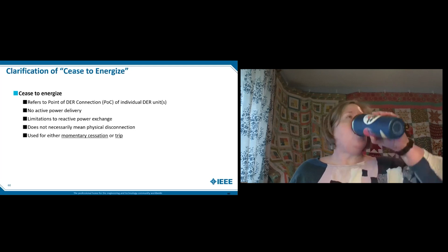Now, I worked for a utility where at solar noon on suburban feeders, where everyone's at work or gone and PV is at maximum output, we were getting voltage lift to the point that, yes, we had to stop adding PV. And we didn't use voltage regulators or load tap changers. But here's an interesting idea in Alaska. Solar noon could go for many, many hours during the summer. So I would imagine there could even be more drivers to make sure that they're leveraging, accessing, and using the voltage VAR controllability, to make sure that you don't inadvertently run into a barrier to adding more PV.